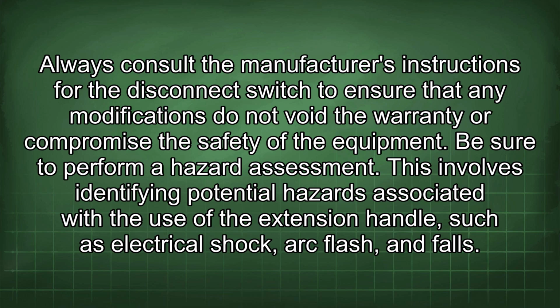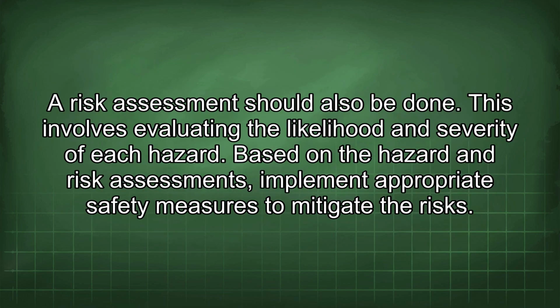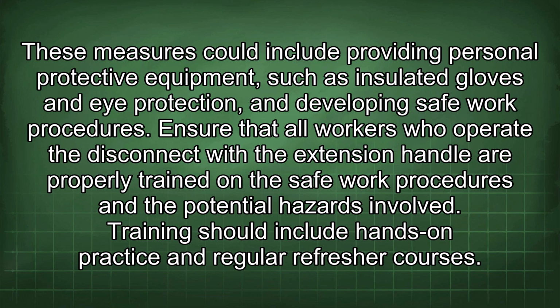Be sure to perform a hazard assessment. This involves identifying potential hazards associated with the use of the extension handle, such as electrical shock, arc flash, and falls. A risk assessment should also be done. This involves evaluating the likelihood and severity of each hazard. Based on the hazard and risk assessments, implement appropriate safety measures to mitigate the risks. These measures could include providing personal protective equipment, such as insulated gloves and eye protection, and developing safe work procedures.